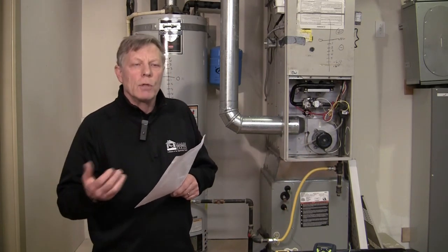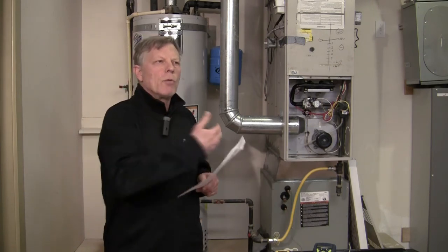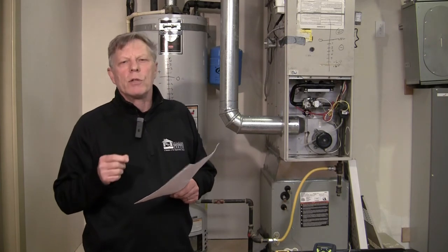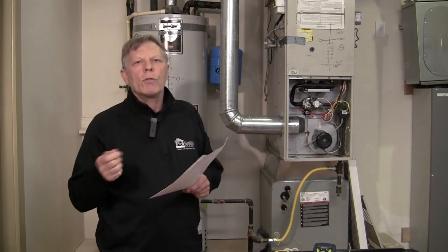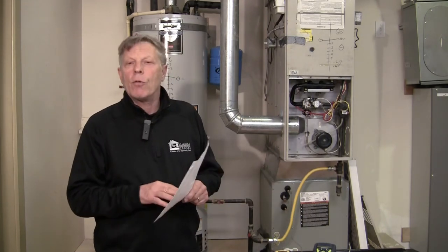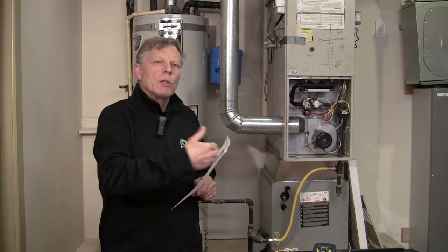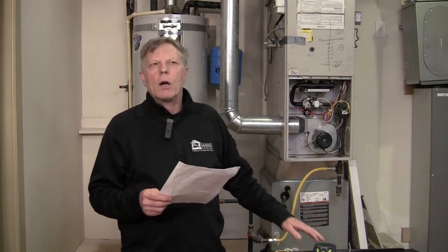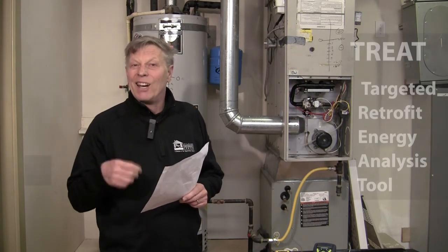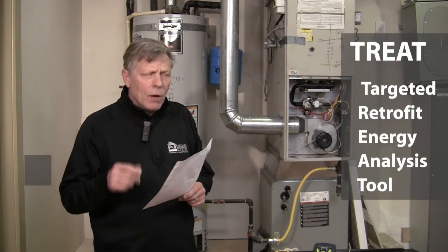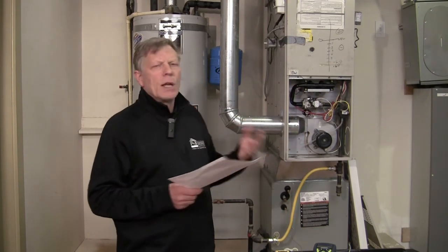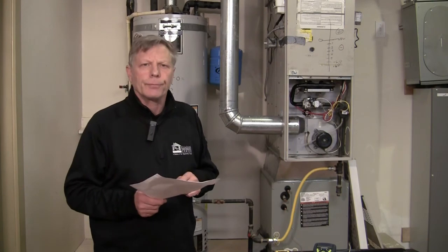Now, depressurization testing, of course we depressurize to get worst case spillage, but we also do just a depressurization test for wood stoves and fireplaces. That's line 11 on the form. We will be doing combustion efficiency testing with our combustion analyzer. That's just done on furnaces and boilers because we put that in our TREAT audit. And then we do heat rise, which is another safety test on furnaces, but that's for forced air furnaces only.